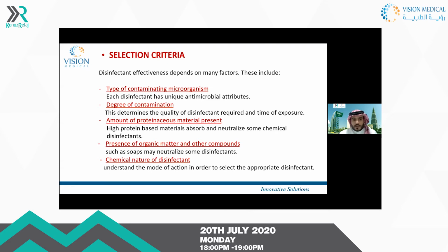We need to define and know which microorganism we are dealing with in the CSSD by doing a test. Each disinfectant has unique antimicrobial attributes, and the degree of contamination determines the quality of disinfectant required and the time of exposure. The amount of proteinous material present matters, since high protein-based material can absorb and neutralize some chemical disinfectants. The presence of organic matter and other components such as soap may also neutralize some disinfectants, as does the chemical nature of the disinfectant. We should understand the mode of action in order to select a proper disinfectant.